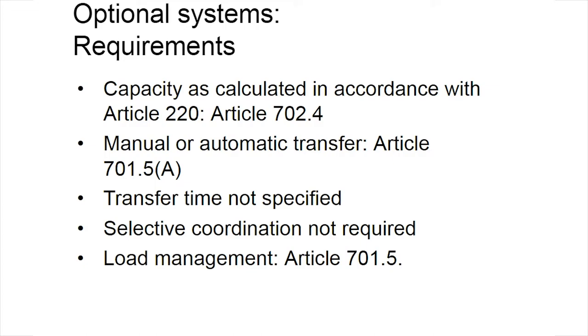The capacity of the optional system is required to be what's calculated in accordance with Article 220 of the NEC. That article is the one that governs service entrance calculations. That's quite a bit less restrictive than the emergency systems requirement of being ready to serve all loads at once. It could wind up being more restrictive in practice than the all loads intended to operate at one time rule for legally required standby. Most service entrances sized in accordance with Article 220 have plenty of headroom, so we can expect that the same calculations will lead us to generators with some level of extra capacity.